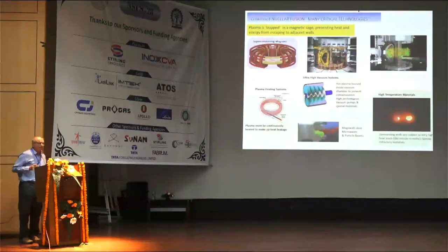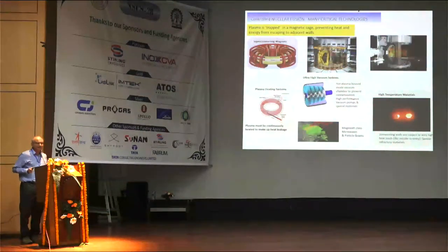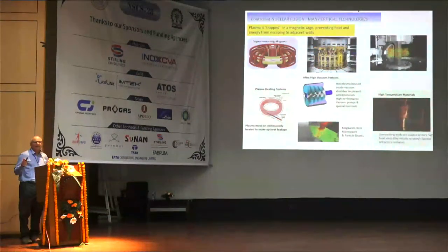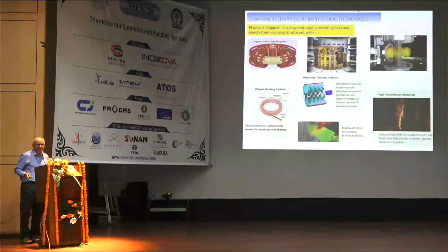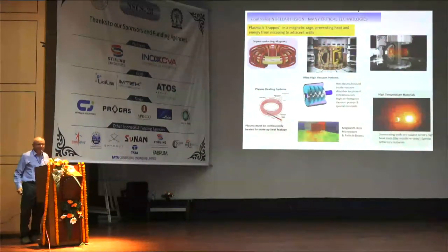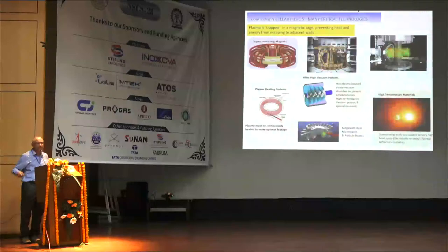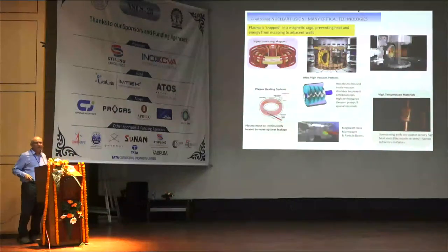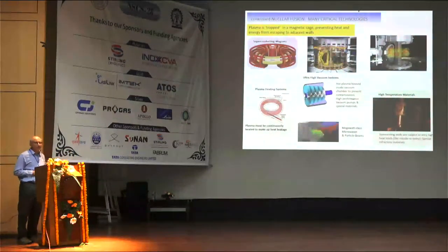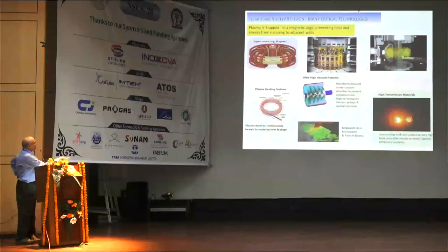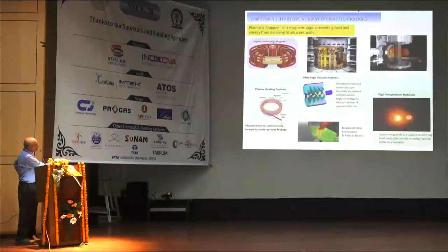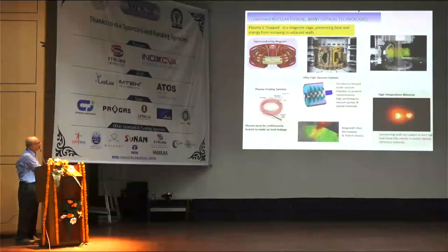Now, these plasmas have to be kept at very low density, about 1 lakh times lower than the atmosphere. So you need ultra high vacuum systems, and these are very large systems, tens of cubic meters, going down to 10 to the minus 8 millibar. For that, you need high performance vacuum pumps and special materials.